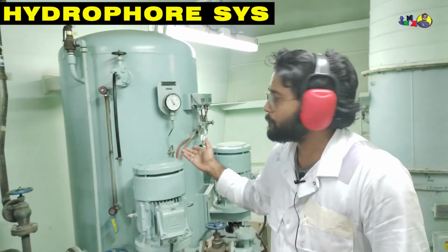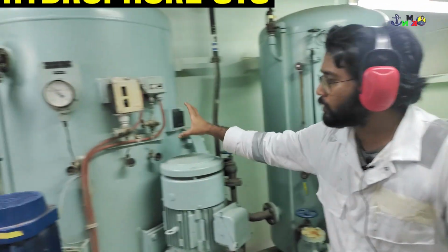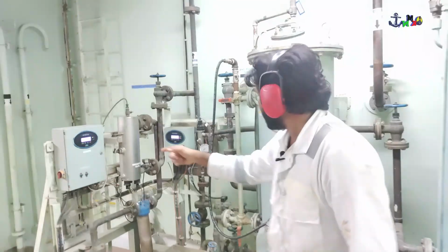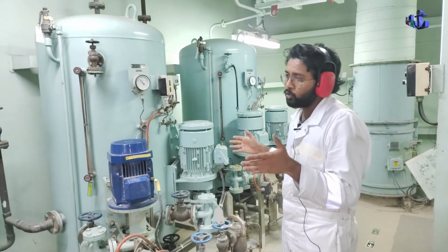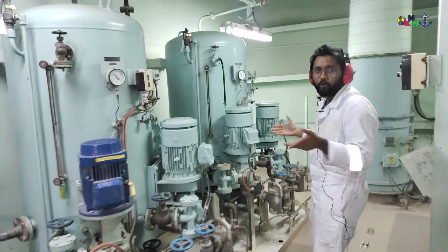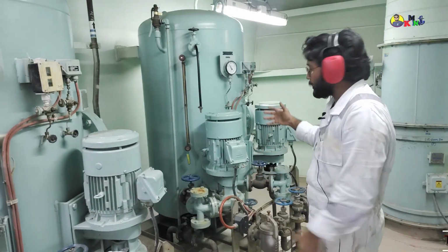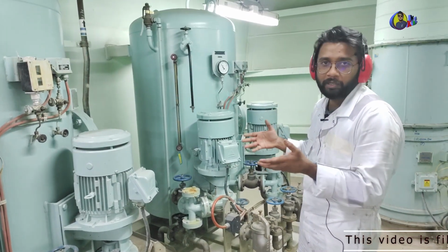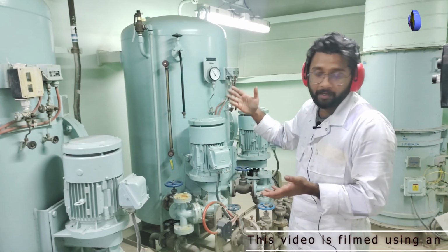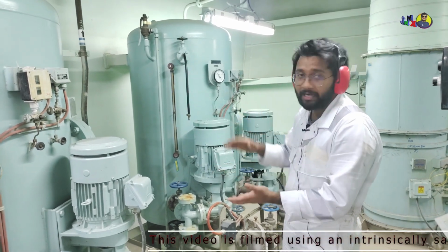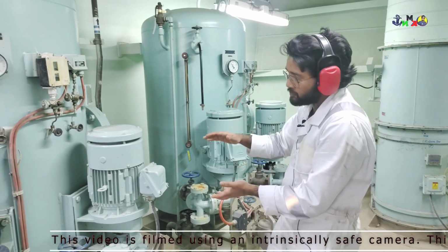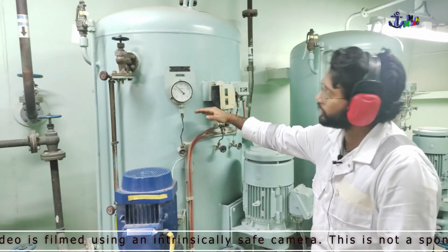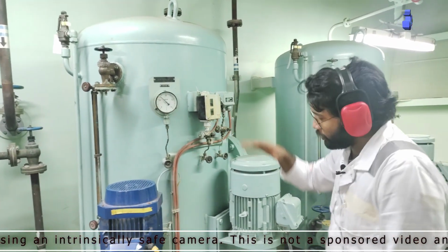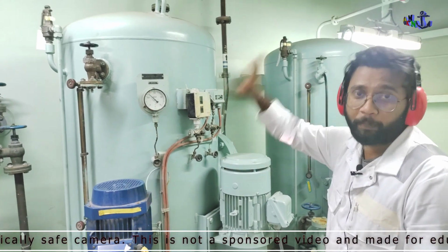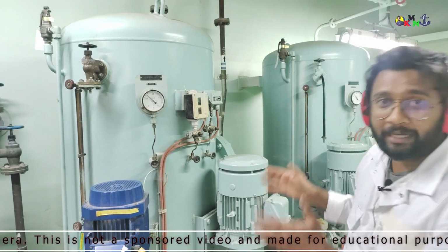These are called hydrophore tanks. This is the freshwater hydrophore, this is the drinking water hydrophore, this is the sterilizer, and this is the mineralizer. This entire system is for supplying fresh water and drinking water to the accommodation and to the ship. Hydrophores are basically a pressurized vessel. To pump water to the topmost part of the ship requires too much head, so without a pressurized system you would need a bigger pump. With a small pump and this pressure vessel, water sits inside and air presses it from the top, so you can easily pump water to a particular height, and this way we can utilize less space for the purpose.